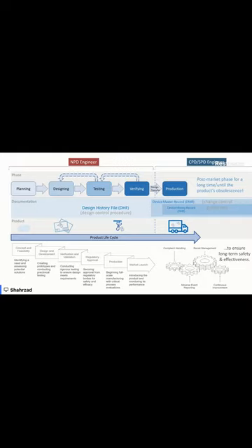And if there is at any point any changes required to the design or to the product, basically, if they test the product and it's not performing as they intended and they need to make modifications and changes, then there's design control procedures, part of the regulatory requirements to work to, right? So the NPD engineer would work in accordance with design control procedure.